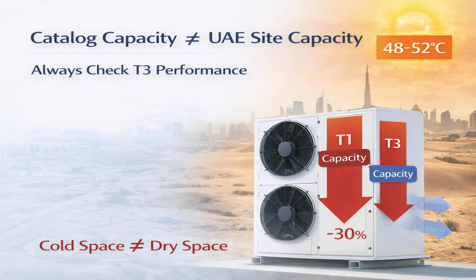In regions like the Middle East, HVAC equipment is exposed to much harsher conditions. This is where T3 conditions become critical. T3 performance accounts for much higher outdoor ambient temperatures, higher condenser entering air temperatures, and increased compressor and fan loading. Under T3 conditions, the same unit delivers less cooling capacity and consumes more power than it does at T1.